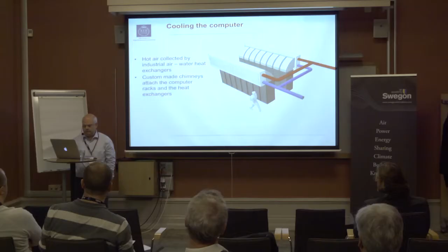So this is a little bit more about the temperature in the system. As we mentioned, we have the raised floor here. We have about 16 degrees under the floor. The racks have fans in them, and they suck up air from below, and out comes something around 44 degrees Celsius. And we collect that with the chimney, and the air goes through the heat exchanger and comes out room neutral again at 21 degrees. And we get out water which is around 30 degrees, which worked really well.